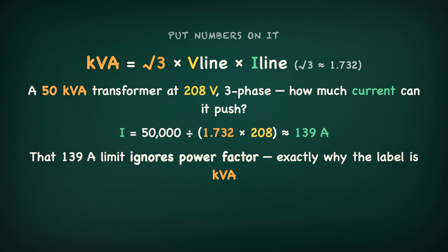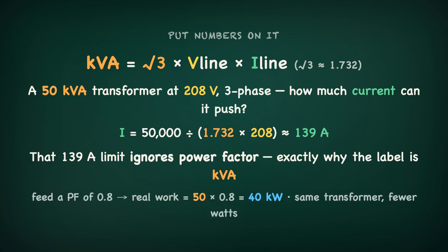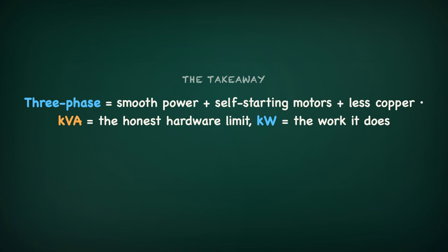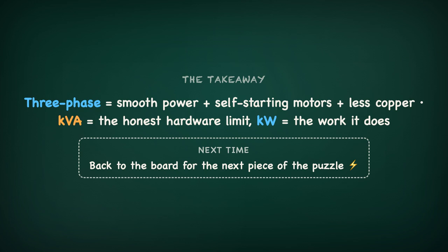Feed it a power factor of 0.8 and the real work it delivers is 50 times 0.8. 40 kilowatts. Same transformer, fewer watts. So, three phase gives you smooth power, self-starting motors, and less copper. And kilovolt amps is the equipment's honest limit, while kilowatts are the work it happens to do. Remember, kilowatts equals kilovolt amps times power factor.